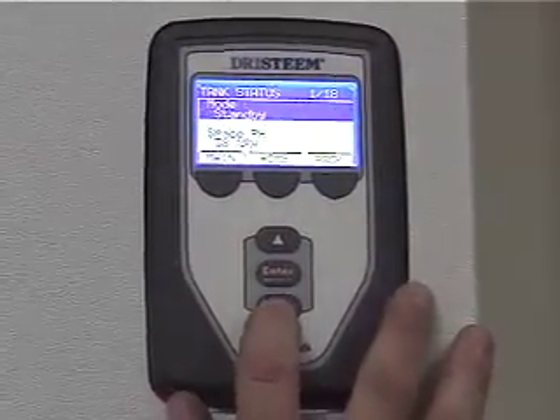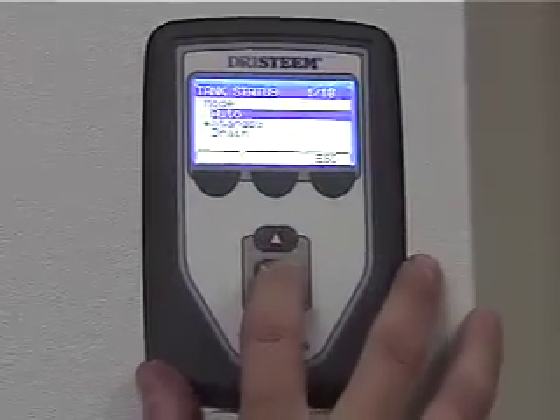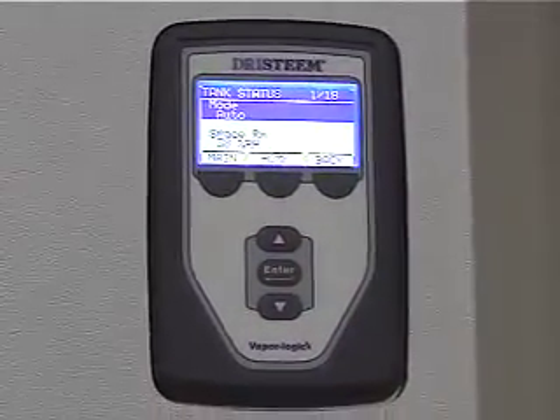The mode is in what? Standby mode. Standby, is that good? No. Never run it in standby. Auto. Now our fan's going to kick on. Even though it's not making humidity yet, they don't want steam condensing in there, so they always turn the fan on right off the bat, even though it's going to take an extra minute.